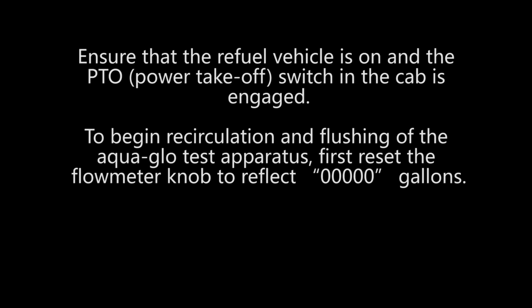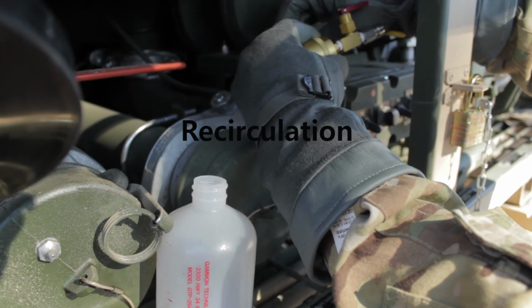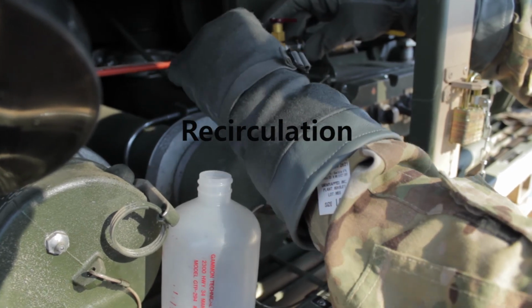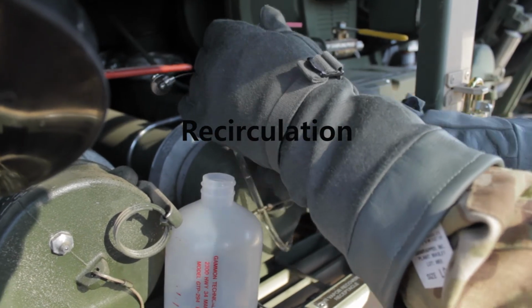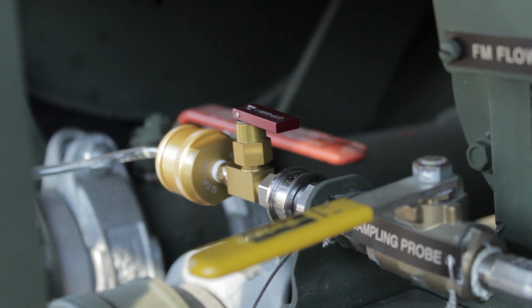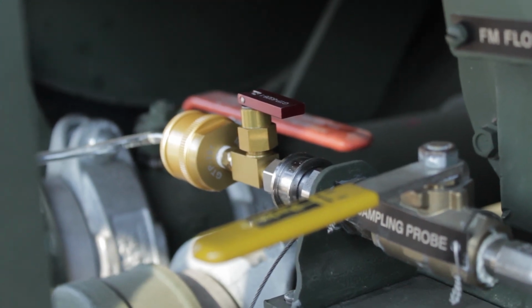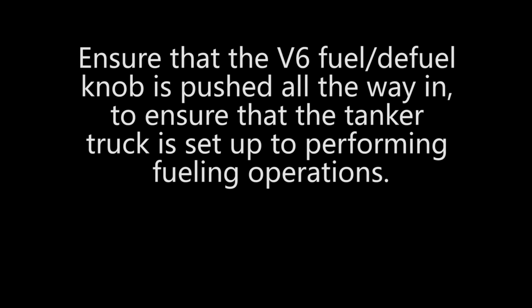To begin recirculation and flushing of the Aqua Glo test apparatus, first reset the flow meter knob to reflect 0 gallons. Couple the sample test probe to the sampling connector. Ensure that the toggle valve on the connector is closed, perpendicular to the line. Ensure that the V6 fuel defuel knob is pushed all the way in to ensure that the tanker truck is set up to perform refueling operations.